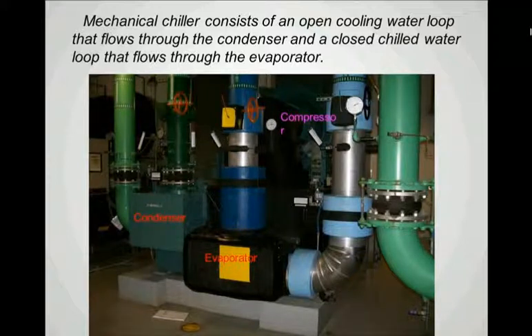So we see here in this illustration the condenser water section of the cooling tower. Water from the cooling tower enters the condenser, passes through the condenser, picks up the heat, and then is pumped back to the cooling tower where that heat is rejected to the atmosphere. There's another section of the chiller called the evaporator, which also is a heat exchanger, and that removes heat from the chilled water loop. So here's an example of one of those heat exchangers.